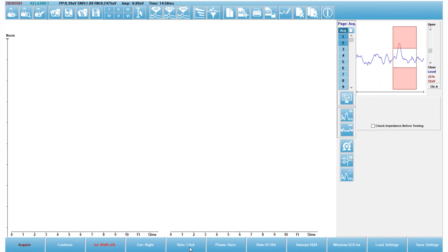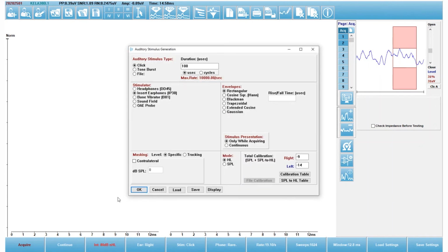If I select the stimulus icon, here's where I would set the transducer. So in this case, it's the insert earphone. And this is also where I would apply masking should I want to add that to the opposite ear. If I wanted to select a different stimulus, I would select it from either tone burst or a file.